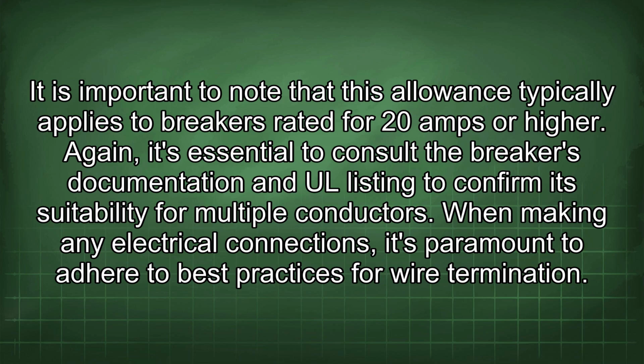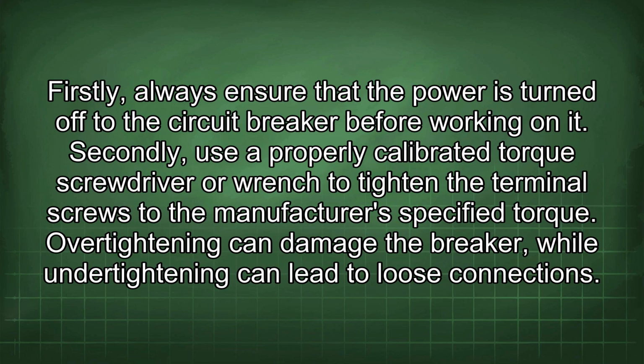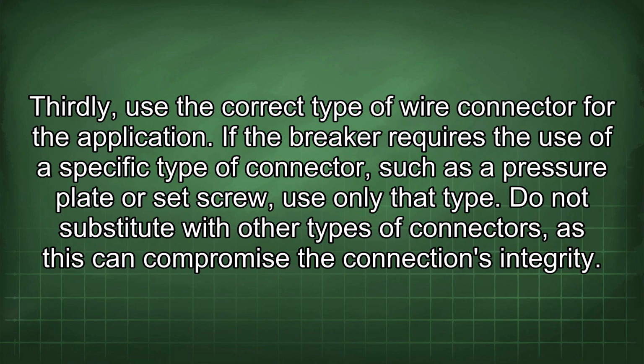When making any electrical connections, it's paramount to adhere to best practices for wire termination. Firstly, always ensure that the power is turned off to the circuit breaker before working on it. Secondly, use a properly calibrated torque screwdriver or wrench to tighten the terminal screws to the manufacturer's specified torque. Over-tightening can damage the breaker, while under-tightening can lead to loose connections. Thirdly, use the correct type of wire connector for the application. If the breaker requires the use of a specific type of connector, such as a pressure plate or set screw, use only that type. Do not substitute with other types of connectors, as this can compromise the connection's integrity.